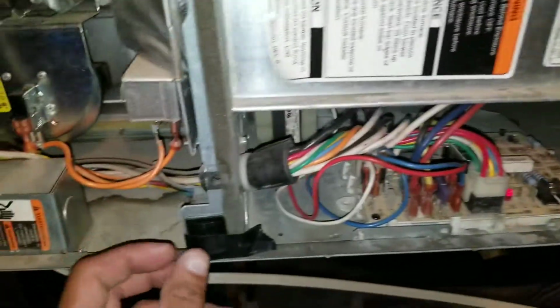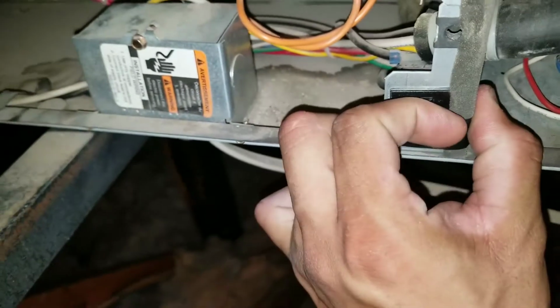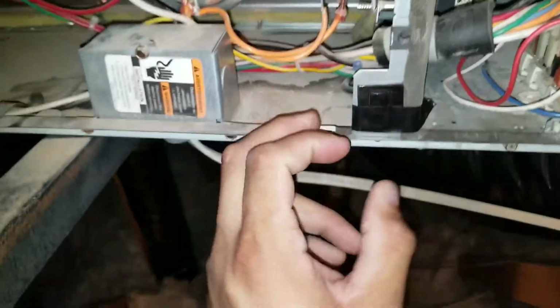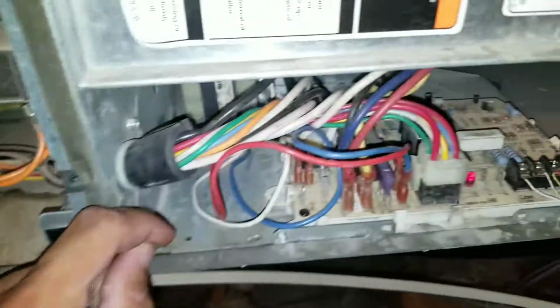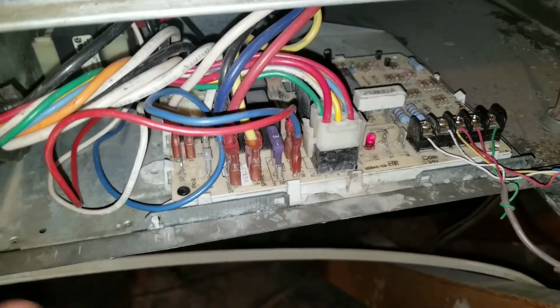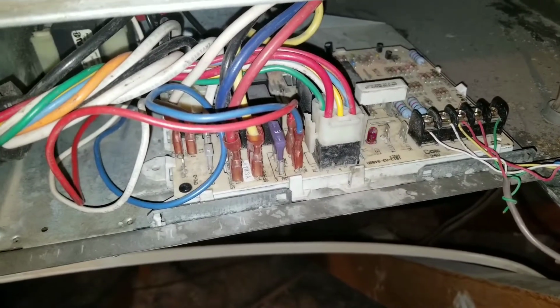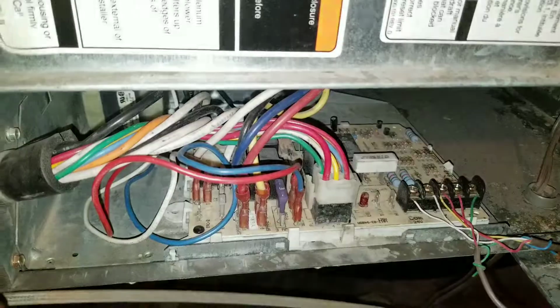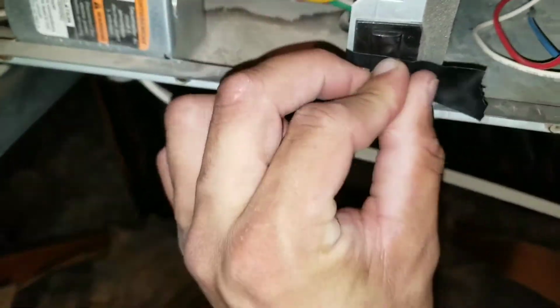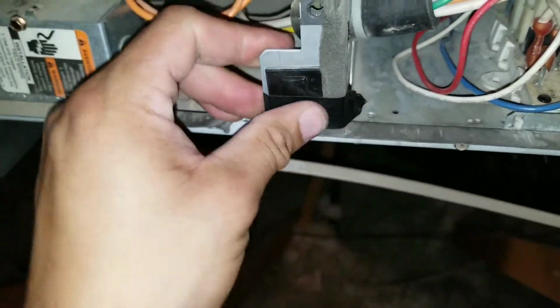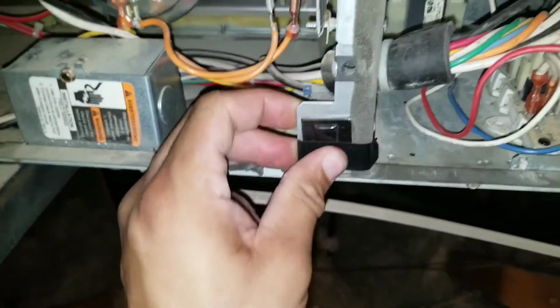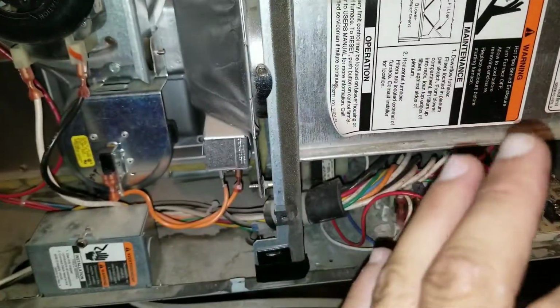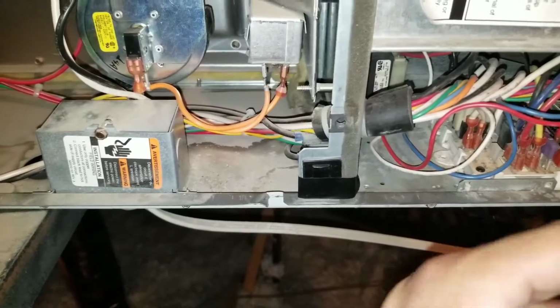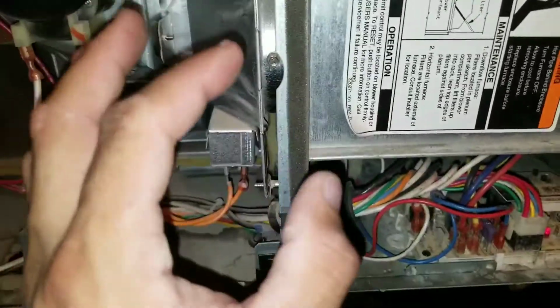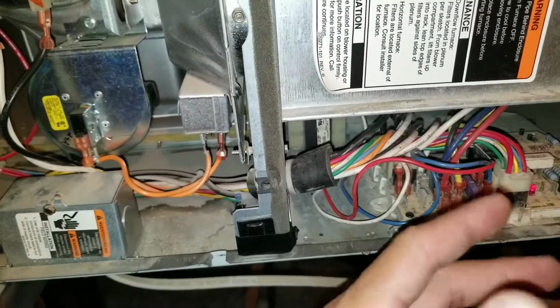Right now I did put electrical tape over my safety switch. If this switch is not engaged, you can see here my LED light is in the on position. Once I take my tape off, that will remove any power going to my furnace board. Here we want to make sure that the switch is engaged, and this will send power to the furnace board. Now this basically is a safety switch. Usually, once you remove your panel, this switch activates in order to remove power to your board, to your furnace, to protect the technician who's working or servicing the unit.